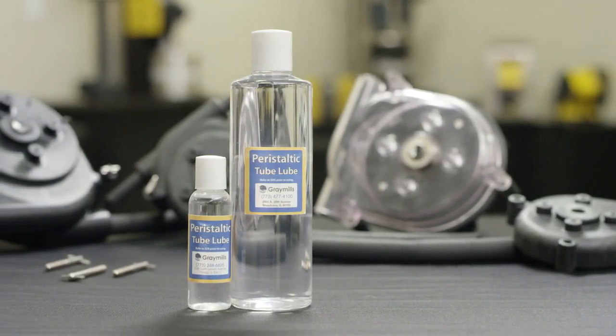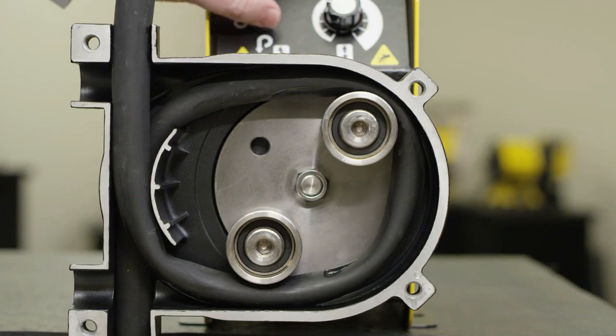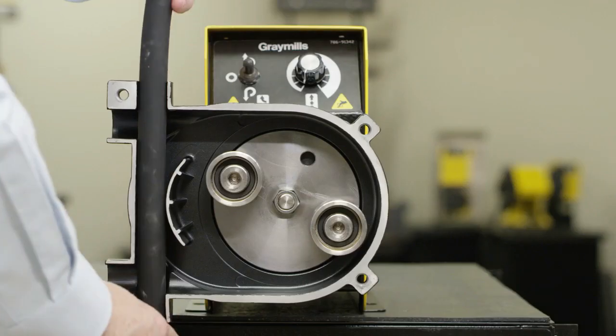Graymills recommends the use of a non-petroleum based lubricant to assist the rotor while compressing the tubing. The lubrication will help the tube to spring back after compression. The tube should also be moved up or down about an inch during use to prevent the rotor from hitting the same pressure point continuously.